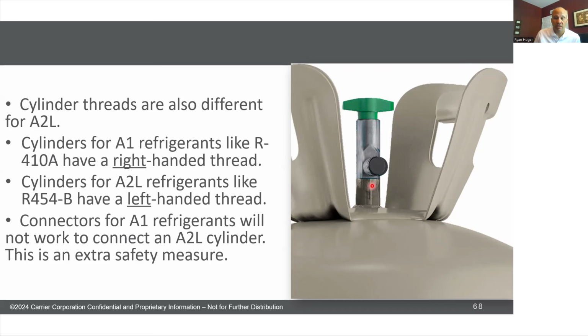And that's annoying. The gauges that you're going to have, your refrigerant gauges, are still right-hand threaded. The equipment, the condensing unit, is still right-hand threaded. Your blue, red, and yellow hoses are still all right-hand threaded. Just this is left-hand threaded. So you will need an adapter to convert your yellow hose to connect to the refrigerant cylinder.